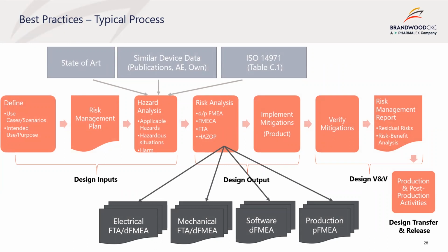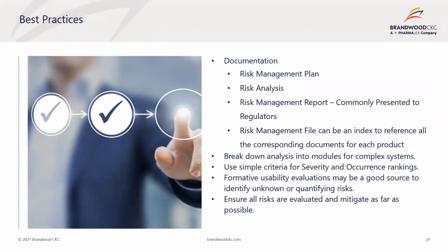Finally, production risks would be identified during design transfer, but it is recommended to start much earlier, say during the design phase, as the manufacturing processes are being designed. Once the product is released, the post-production activities can commence. Here are also some helpful best practices. Firstly, ensure the following documentation is in your risk management file: the risk management plan, the risk analyses, which may be multiple documents, the risk management report, which is commonly presented to regulators, and the risk management file, which can be an index to reference all the corresponding documents for each product or family of products.